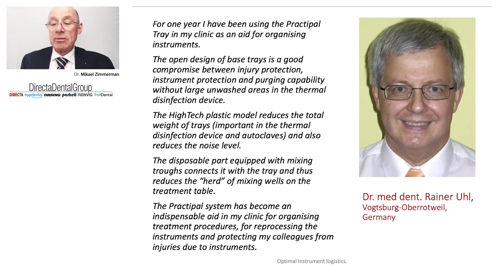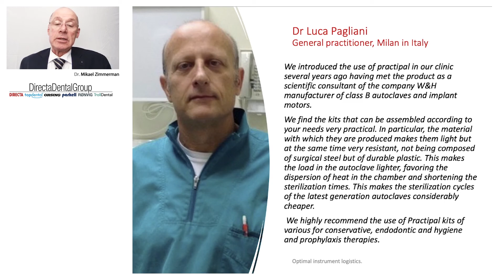Tray systems should also be considered in relation to the sterilization process. Actually, the lighter the load, the less weight you will have in your sterilizer, and it will be a safer process, if not too heavily loaded. A lighter load in your autoclave chamber will also require less energy, and the sterilization cycle will be shortened. This will also be considerably cheaper, using less energy, less time, and being less demanding on the process.